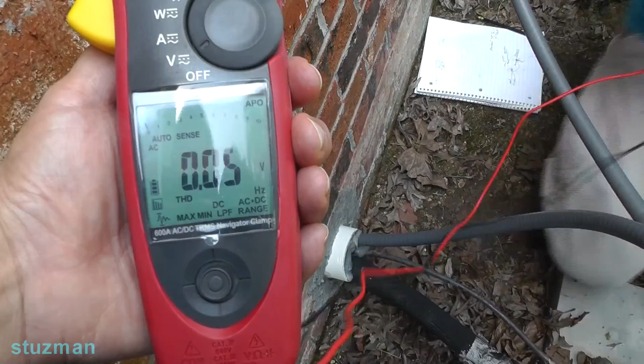I think you can agree that getting the amperage and the voltage on those two capacitors is a lot faster than what we did earlier, shutting the unit down, making sure the power is off, then discharging the capacitor, then pulling the wires off. Where if the unit's running, we just go in there, get our voltage readings and amps, and we're done. So let's go inside and look at the calculations and see how well it checks with the meter that we used initially.